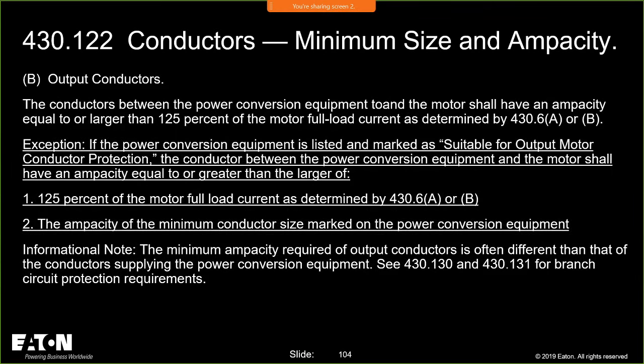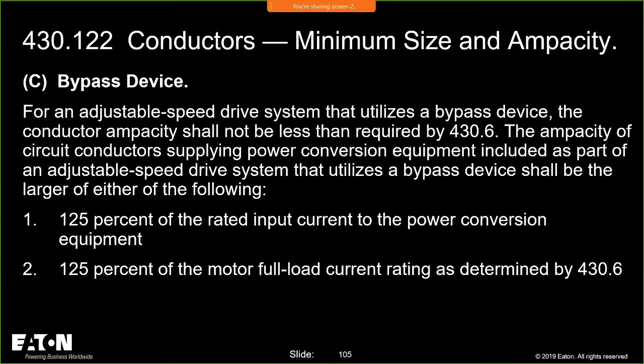In 430.122(B), we provided an exception to the 125%, when it's suitable for output motor conductor protection when the conversion equipment is listed for it. So there are some variable frequency drives and some drive equipment that will say we will protect that, they'll be listed for that, and they give us a separate way to ascertain the ampacity for the calculation of the minimum size and ampacity of those conductors. So you're looking for that. And this did not change, but you're looking for that equipment that has to be rated to provide that protection.